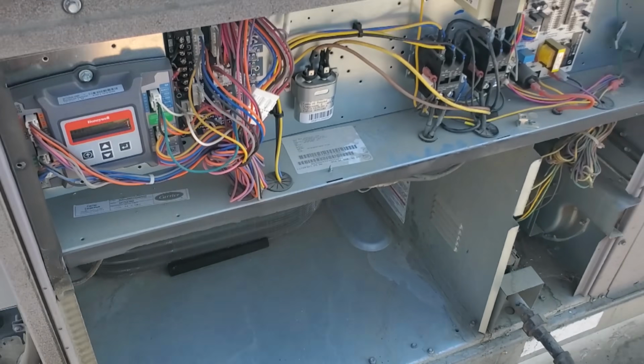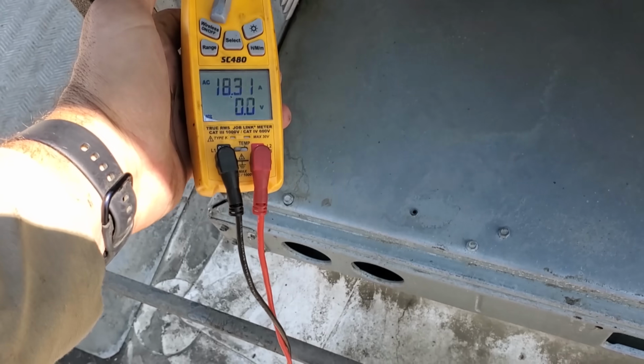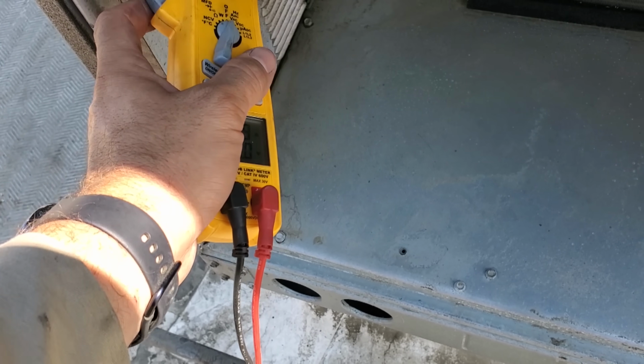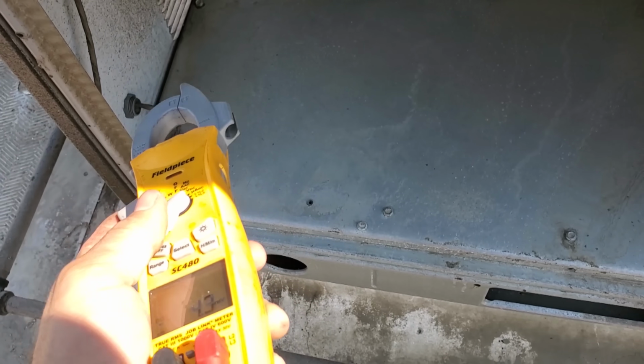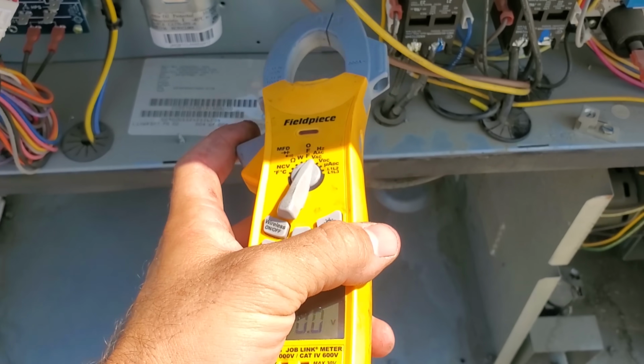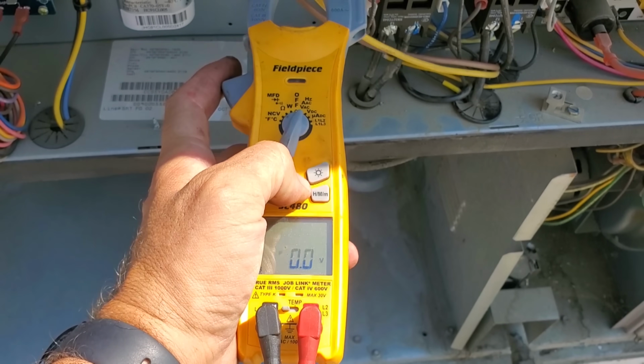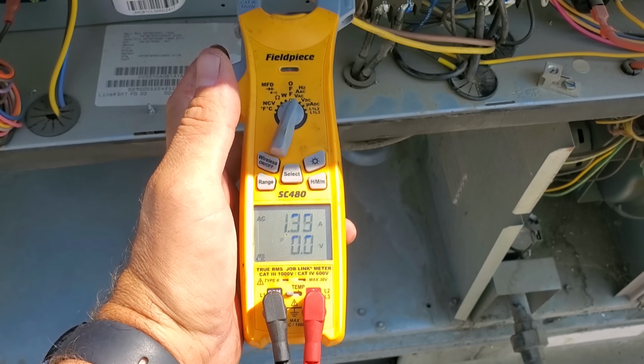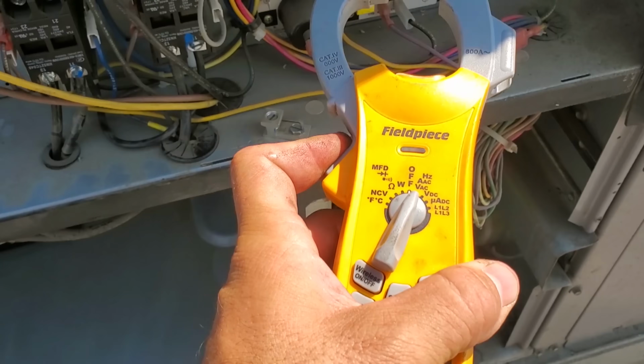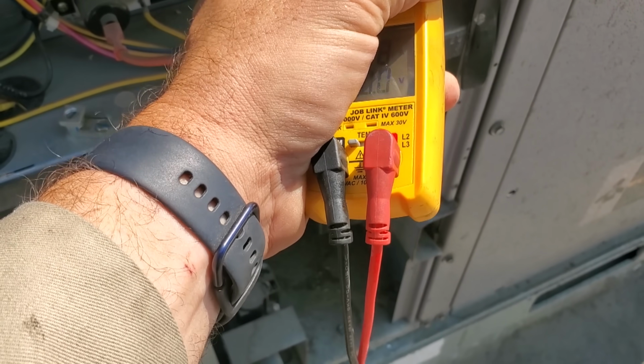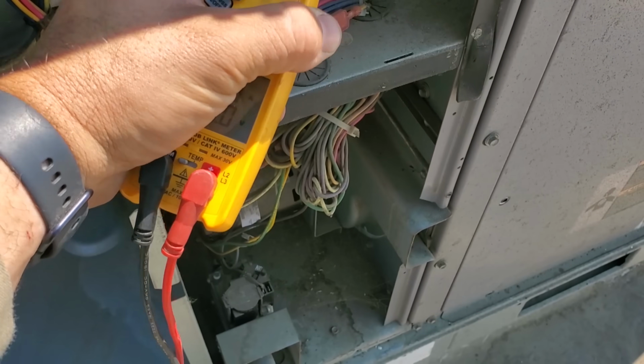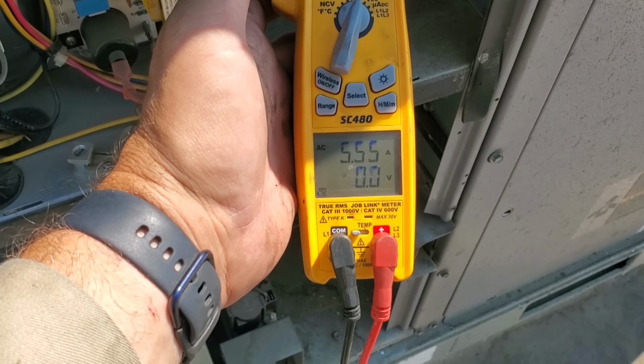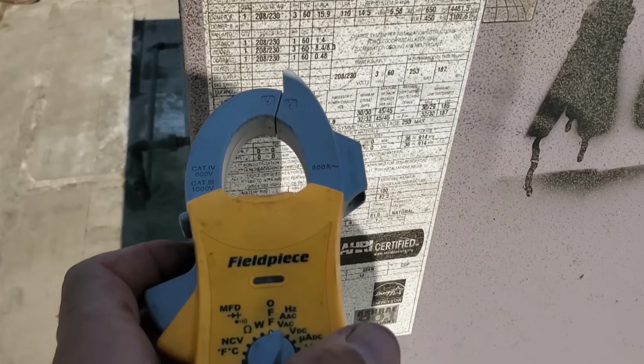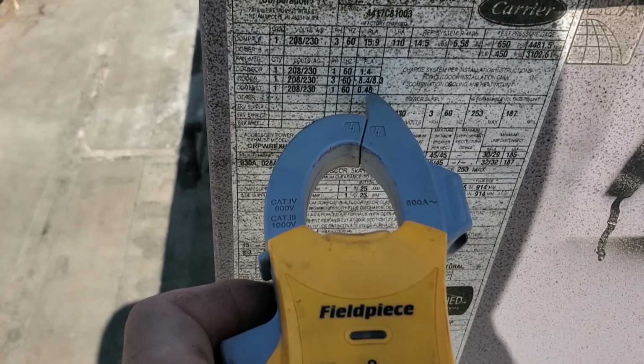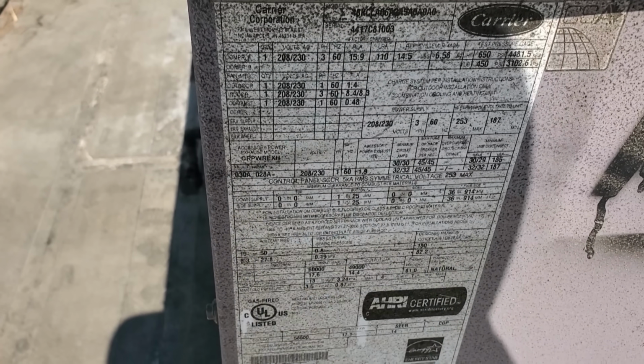Tested current draw and everything. After it's been running for a while, the unit's only running 18, almost 18 and a half amps. That's not a problem at all. We got a 30 amp breaker. Current draw on the condenser fan motor, we're allowed to run 1.7, so that's good. Indoor blower motor, I believe, is allowed to run like 5, or no, it's allowed to run 8, I think. 5.5 is what it's running right now. Indoor motor is allowed to run 4 or 8.4, so we're doing fine.